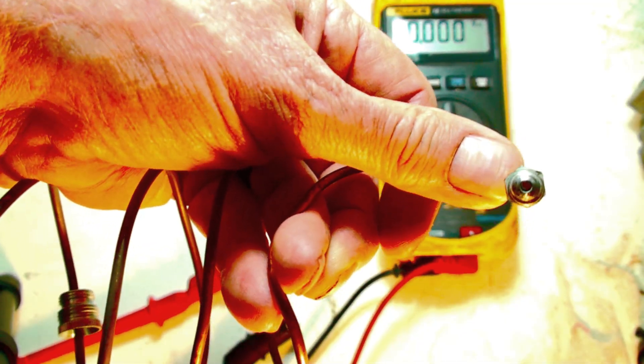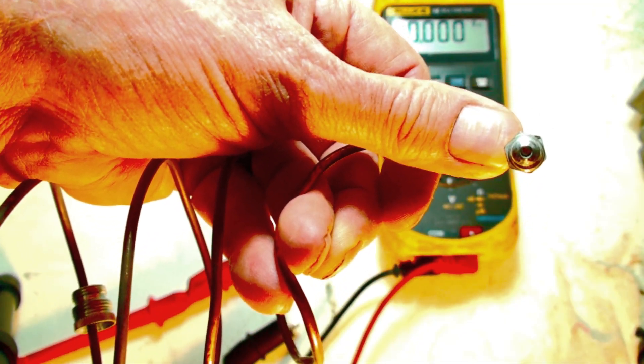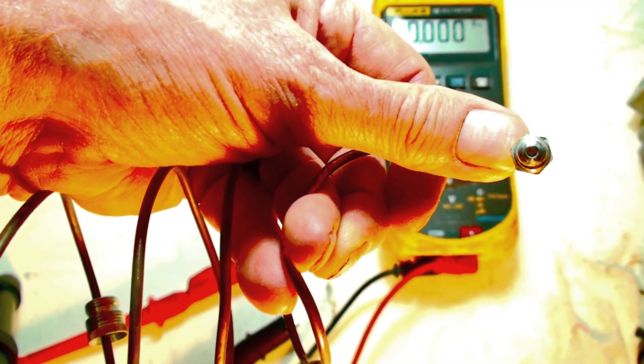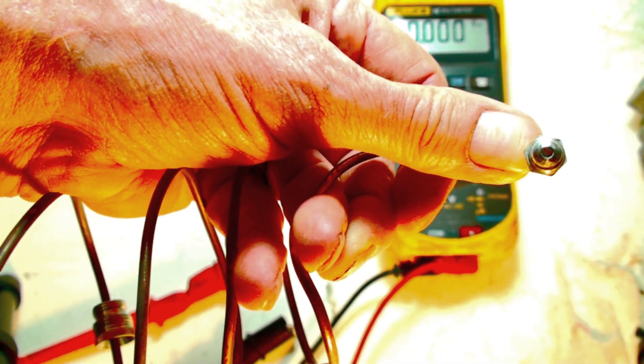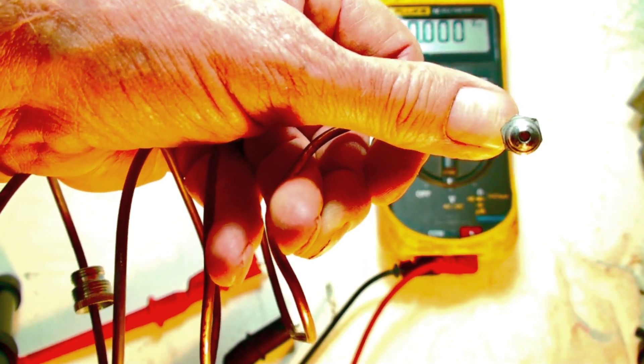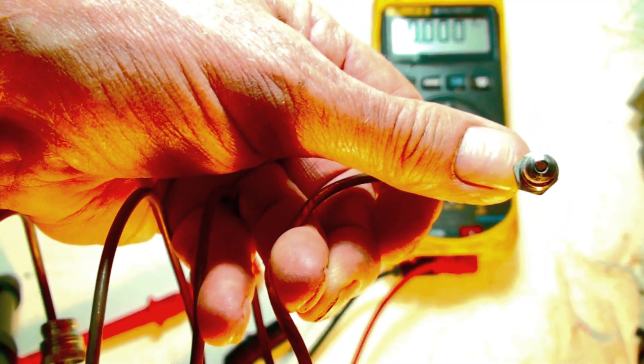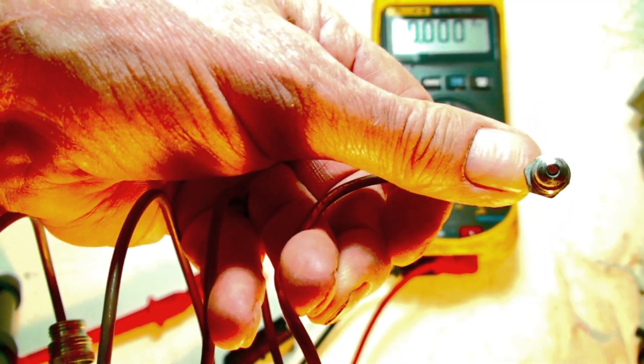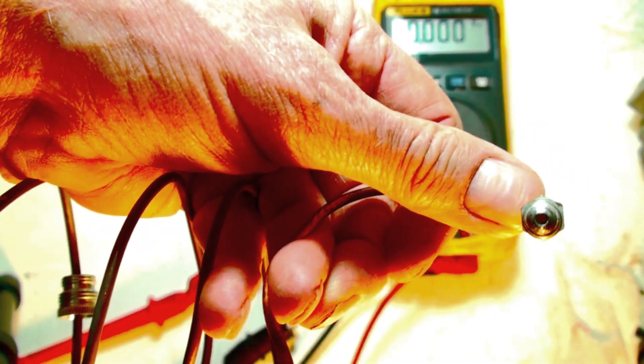As a comparison, a volt-and-a-half flashlight battery is 1500 millivolts, so there's not very much pressure pushing power through this. So the contacts got to be really good. This thing should be tight but don't reef on it hard. It should be snug. Reef on hard sometimes you'll damage them and then they won't work at all. Anyway, that is the thermocouple hooked up to a meter to determine if it's any good.